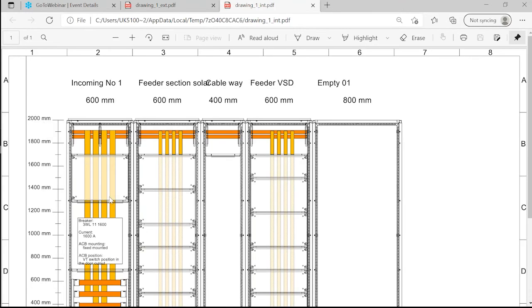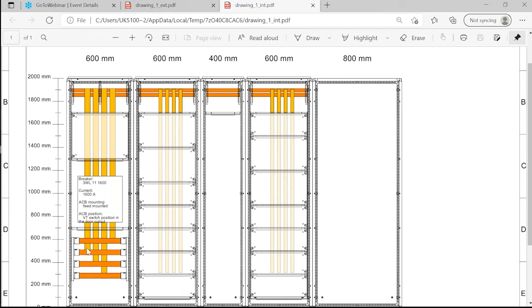This shows the bus bar. So the incoming section, we have the horizontal connections for the incoming cables. On there, you can fit a good number of terminals for lugs for connecting the incoming cables. The ACB circuit breaker is a Siemens 3WL. Current rating is 1600 amps. That's the rating of the breaker. Don't forget it's been derated. And this is a fixed breaker, or it can be withdrawable. I've clicked on fixed there.